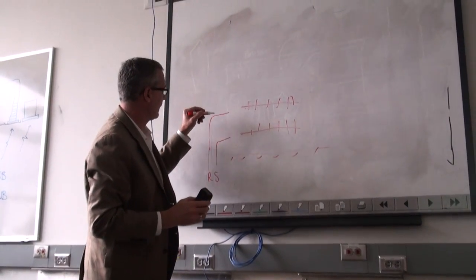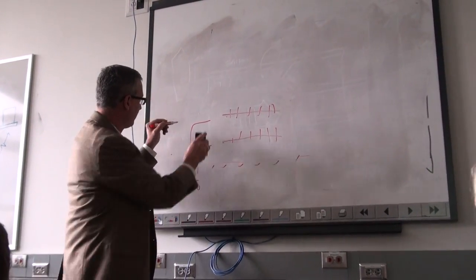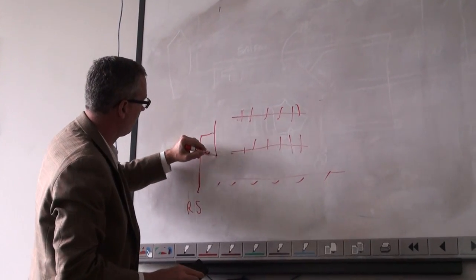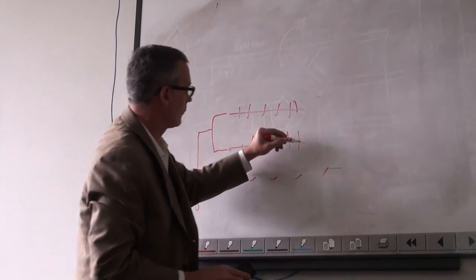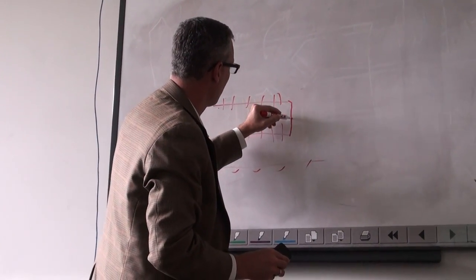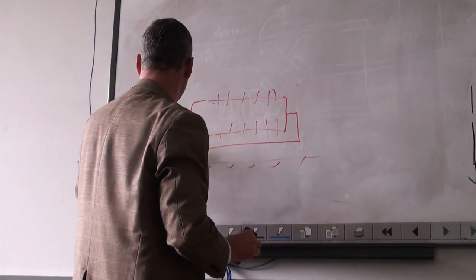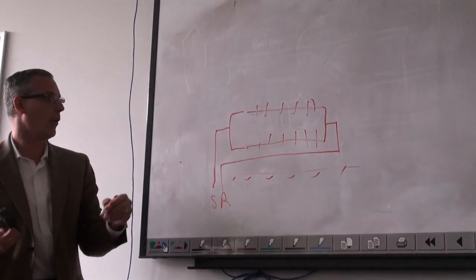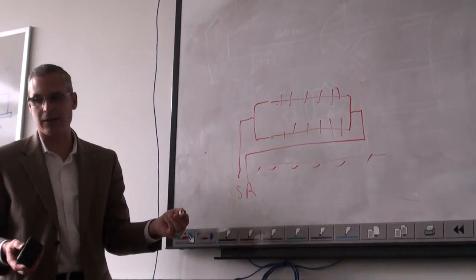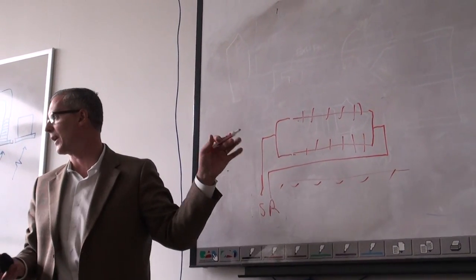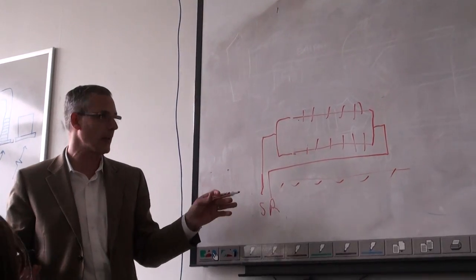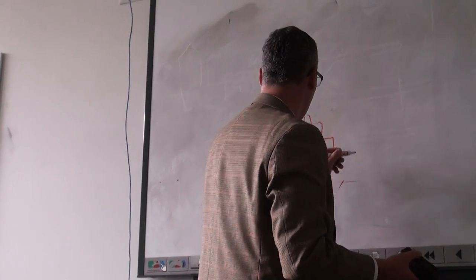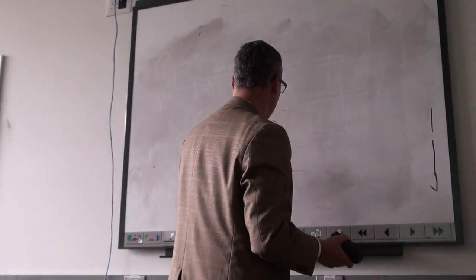So what should be done here is that the supply should have been fed with a manifold, and you should come back with another manifold on the return. Or you talk to the engineer. Sometimes we're talking to the engineer, and they say, you know what, I can't afford that, I don't want to do that, or it's not that critical. Once you tell them what you've got, then you can design it up front. You can say, okay, well, I'm just going to serpentine this.